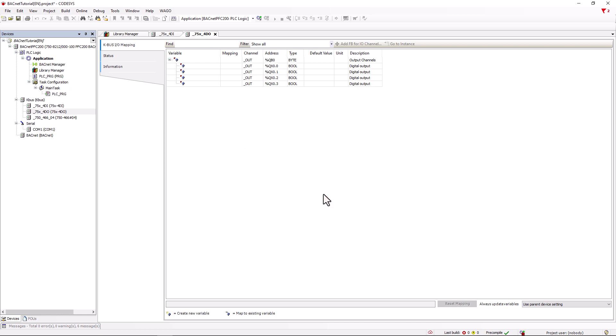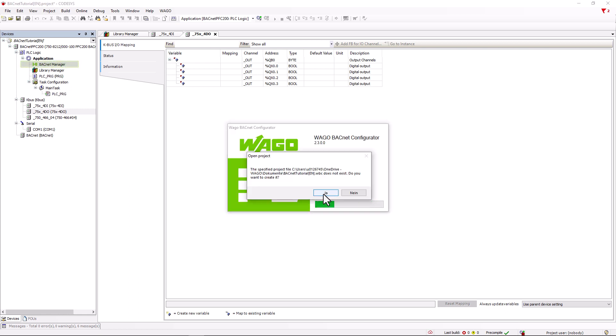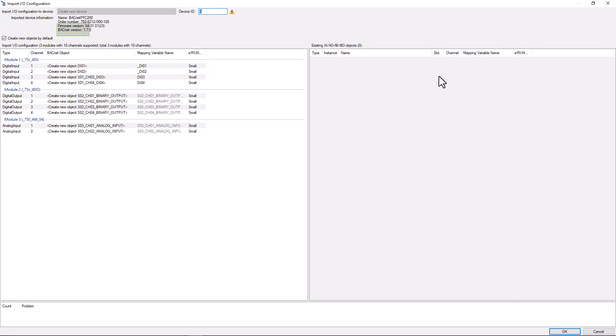First, the BACnet manager is created in the Applications folder. Then, if it does not already exist, a BACnet configurator project folder is created with the same name as the CODESYS project. The controller name, order number, firmware, and BACnet version have already been imported from CODESYS. Each time the controller is rebooted, the corresponding controller is displayed. However, this only works if the name of the controller in CODESYS equals the name in the configurator.